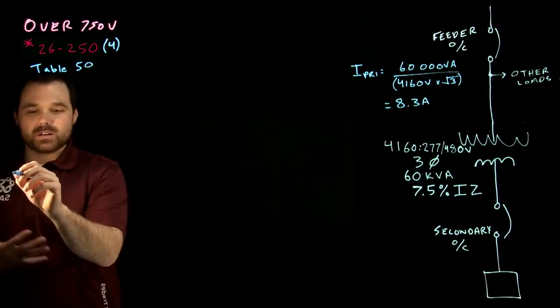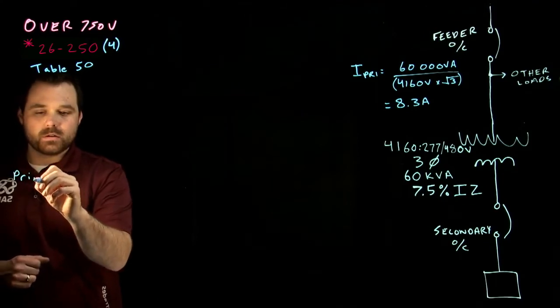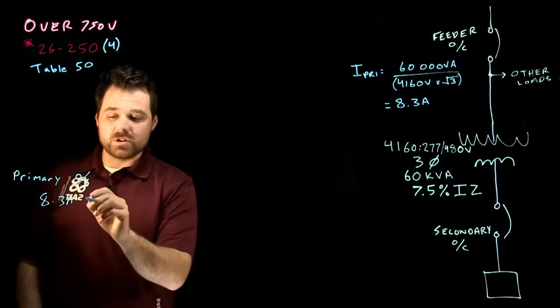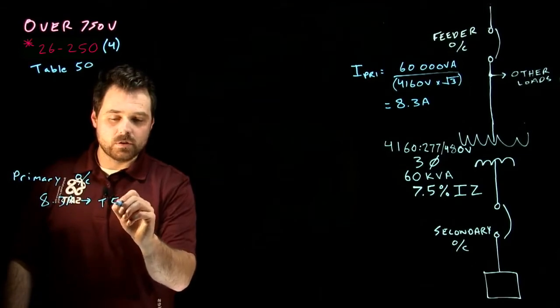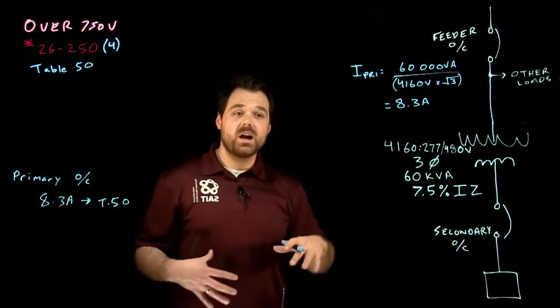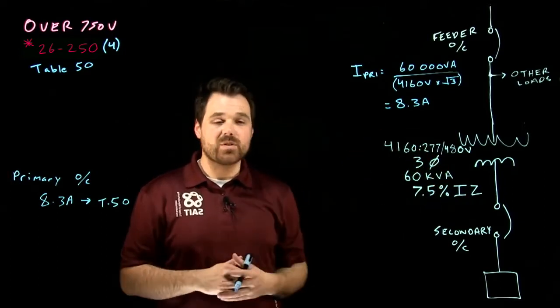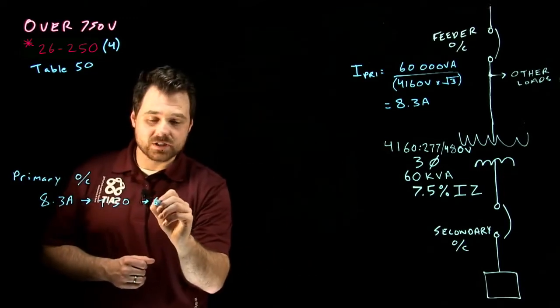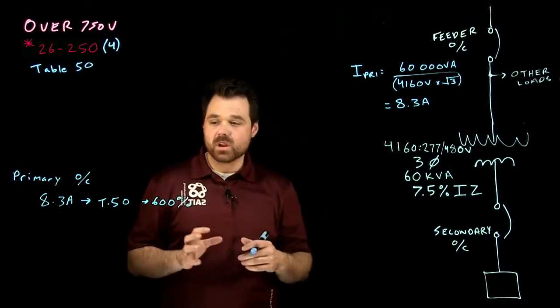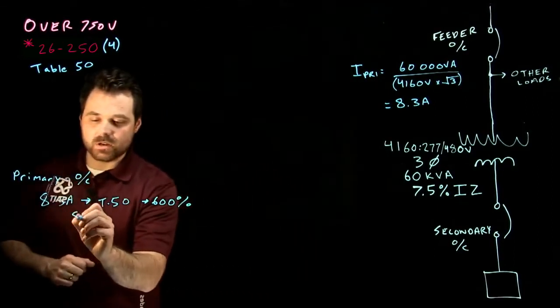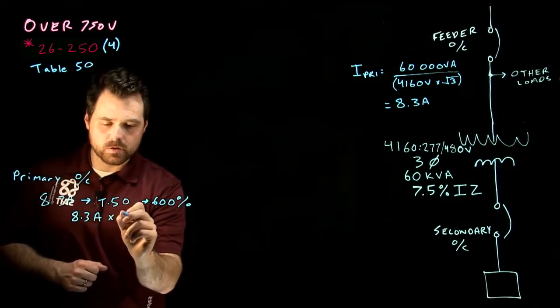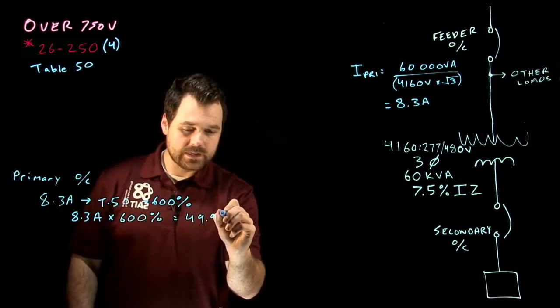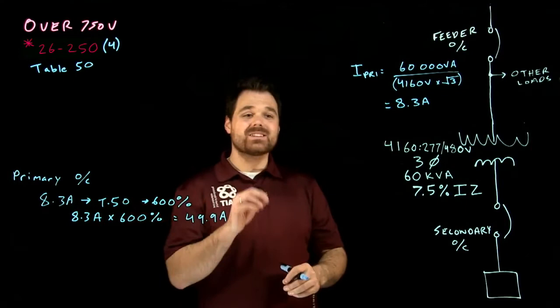What we want to do is take this 8.3 amps. This would be our primary OC. We're going to take 8.3 amps to table 50. Table 50 tells us that in that voltage range with that percent IZ range, 750 or not more than 750, we are actually going to use a 600% multiplier for that. So we go 8.3 times 600%, which is going to give us 49.9 amps. Now, we cannot exceed that rating.